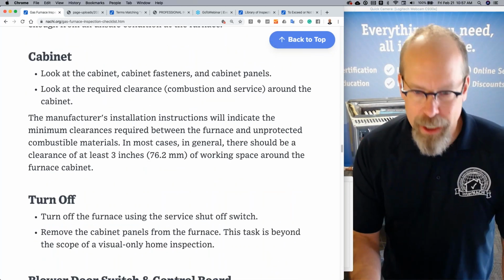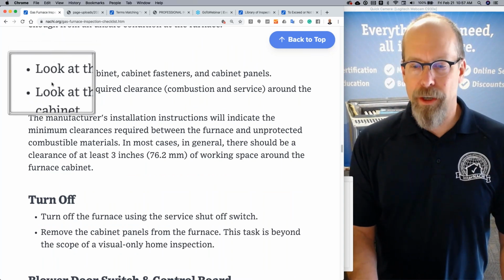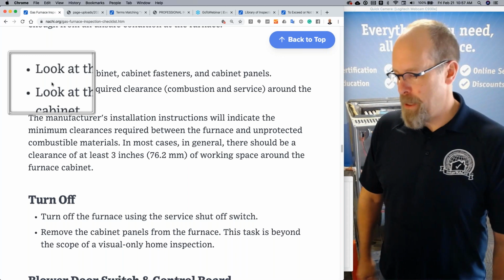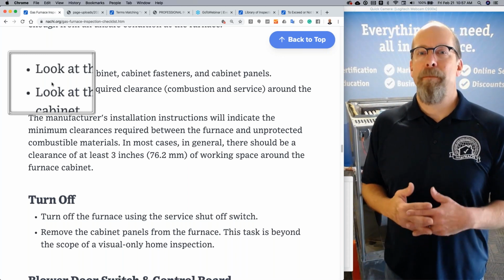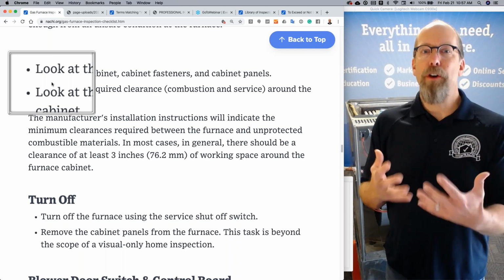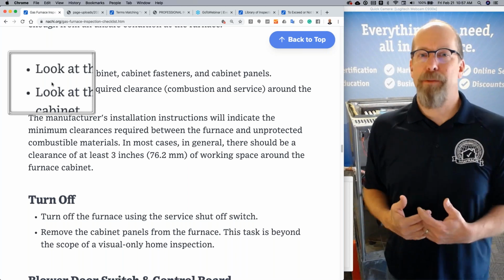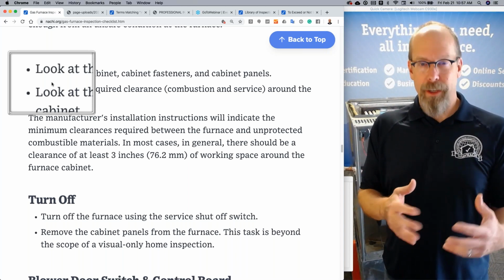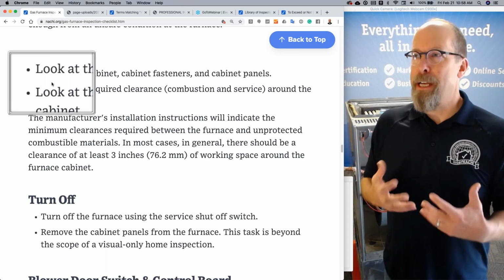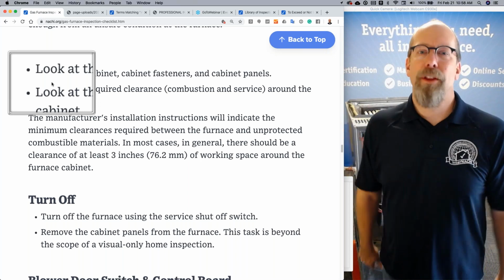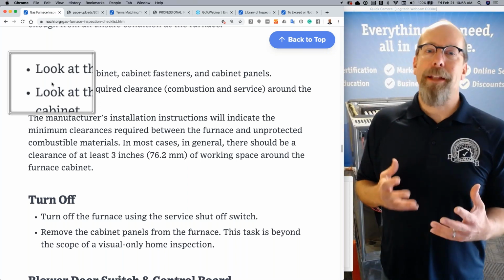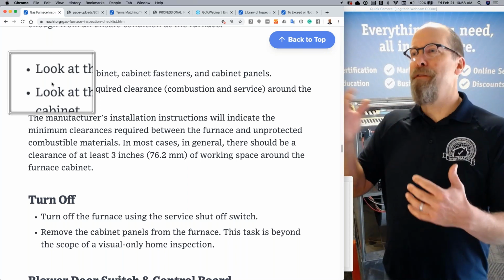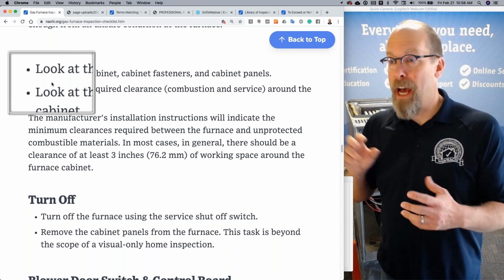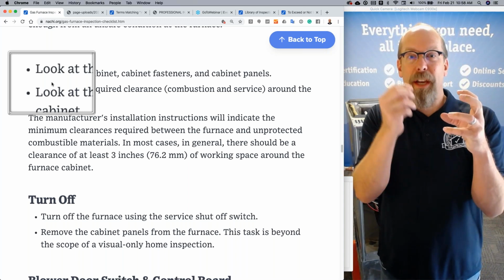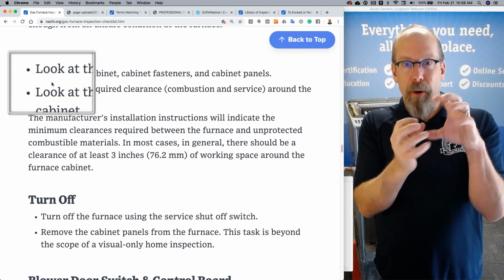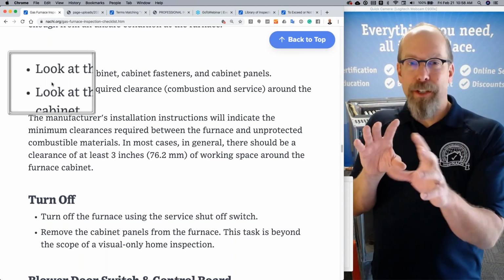So if you see in this checklist, we use a lot of "look." This is a personal opinion: I'm starting to use the word look instead of inspect. Look has a better feel for what I'm trying to say in my inspection report. The word look or looked, because I write in the past tense, I looked at this, I looked at that, is better than inspected. Look at the thermostat, right? I looked at the thermostat. I didn't inspect it, which may convey, in the mind of my client, that I inspected it thoroughly by taking the unit off the wall, looking at the low voltage wires, the connections, taking it apart, looking at the programming, the efficiency of it, the accuracy of it.